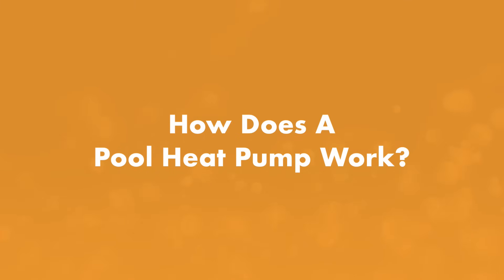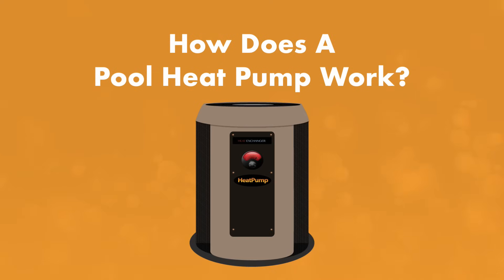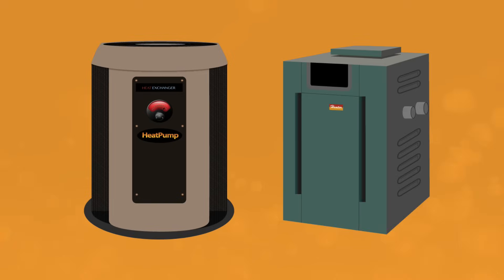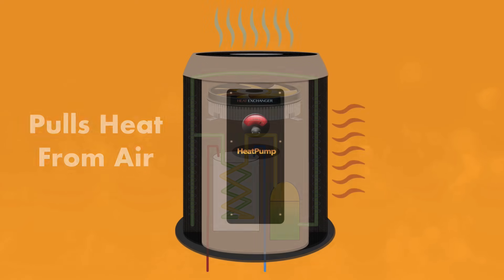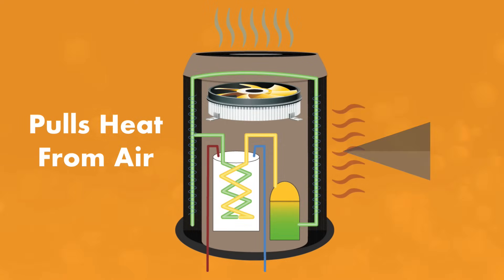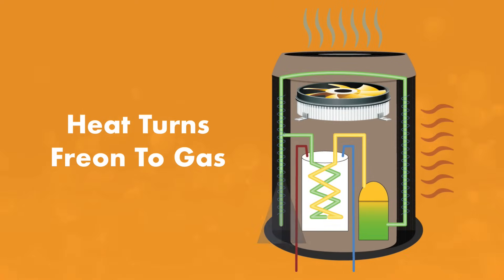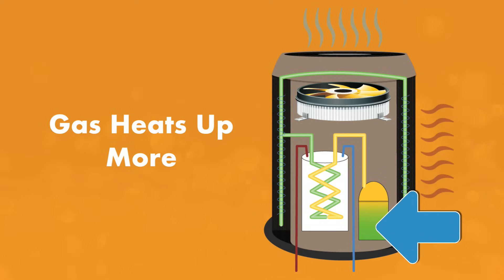First, how does a pool heat pump work? The pump uses electricity and ambient air to heat up your pool water. And unlike a gas heater, pool heat pumps actually don't produce heat. They just transfer it. It's basically like an air conditioner but in reverse. The pool heat pump uses a fan to pull in heat from the outside air. And then the heat is sent to the pump's evaporator coil, where liquid freon absorbs the heat and becomes gas. That warm gas passes through the pump's compressor, where it gets even hotter.